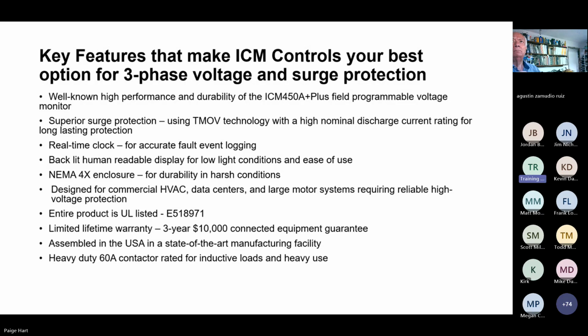Real-time clock means you're going to have accurate fault event logging. That means you're going to get that nice precision that you're looking for. A backlit human-readable display. Can't tell you how important that is. Some of the other models out there that I've seen have dummy lights that are very confusing, and there's an array printed on the front of the control that you have to try to decipher. This is just going to tell you in human-readable English, right on a backlit LCD display: over voltage, line phase loss, line phase over voltage, line reversal. So you're going to see the fault and it's going to be recorded for you. An excellent tool to have when you're out in the field.